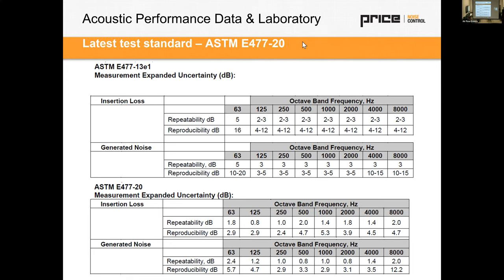What's happened with the latest standard is these ranges and these areas have been tightened quite substantially. And this is a good thing because it shows that people that are testing noise control products and silencer catalog data should be accurate based on how it's captured and cataloged. There were previous versions of the standard as well, back in 2007 and 1999 and 1984, and it goes all the way back until the 60s. As these standards progress and get reviewed and tested and retested, these typically get more stringent. And it's really important that manufacturers are publishing data to this latest standard. We see all the time our competitors, other manufacturers, will have data that's listed to the 1999 version of the standard. And that data is very inaccurate. It's old, it's not as tight as it is now on this latest standard. So I hope that makes sense and it gives you some clarity on that.